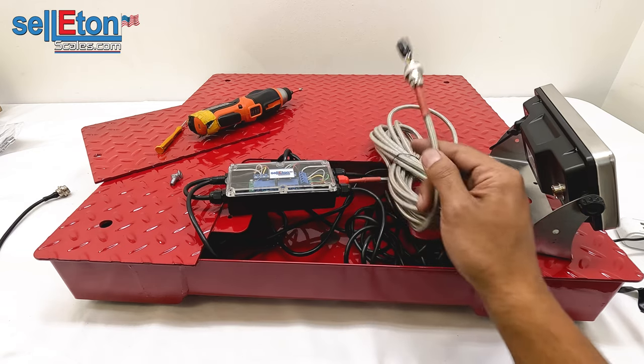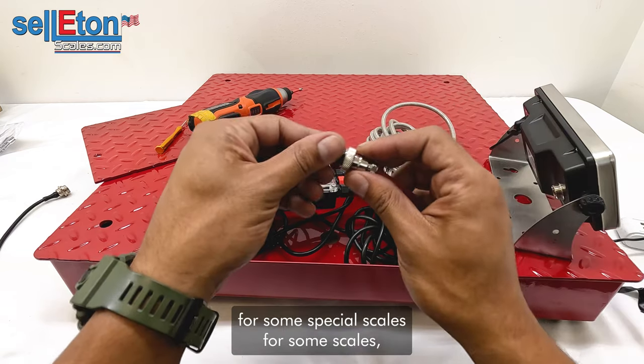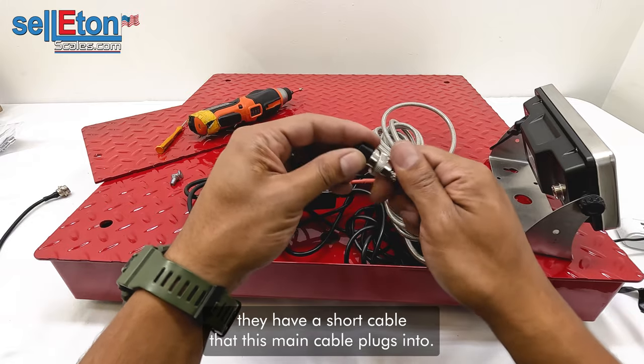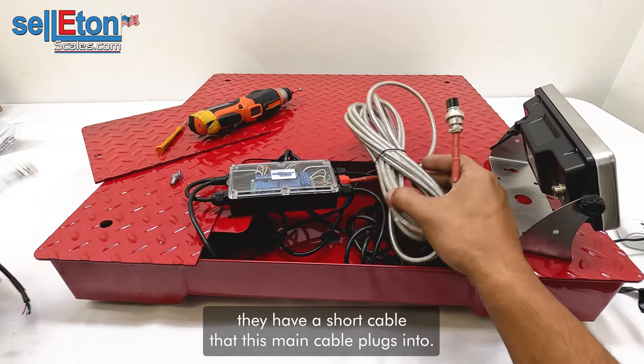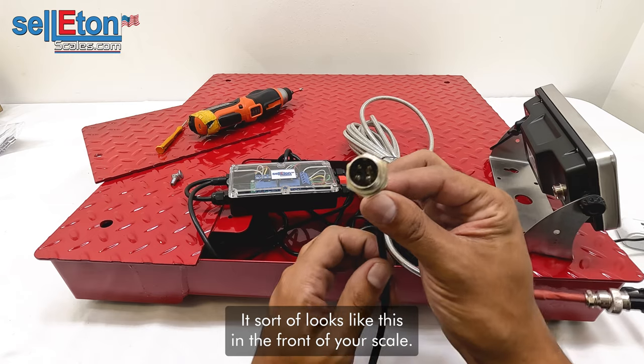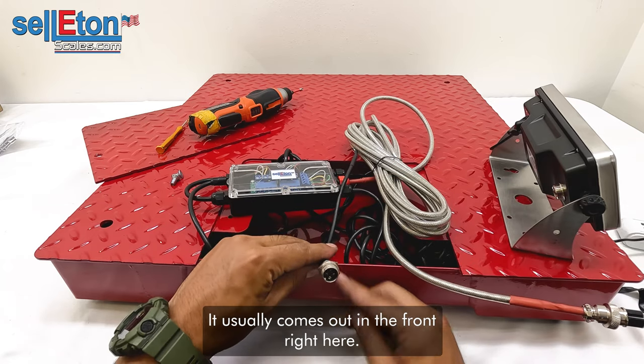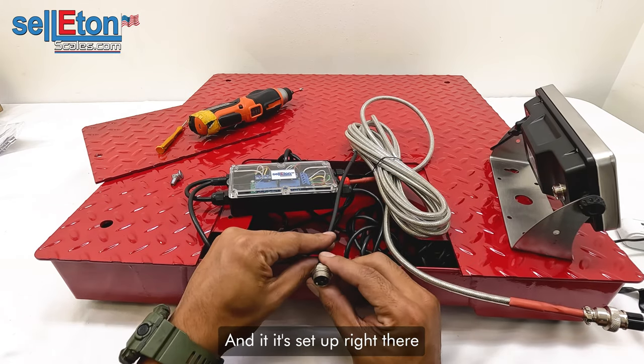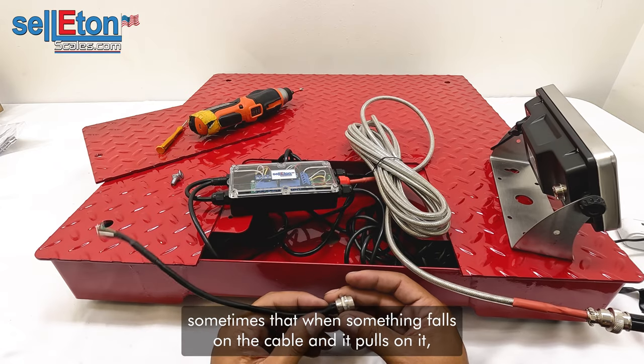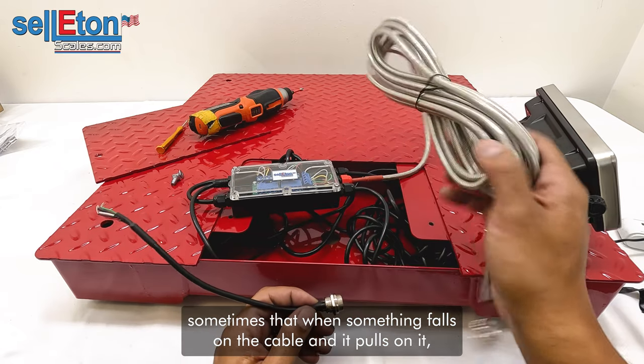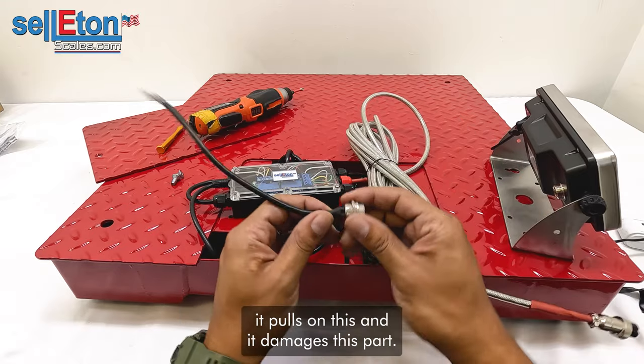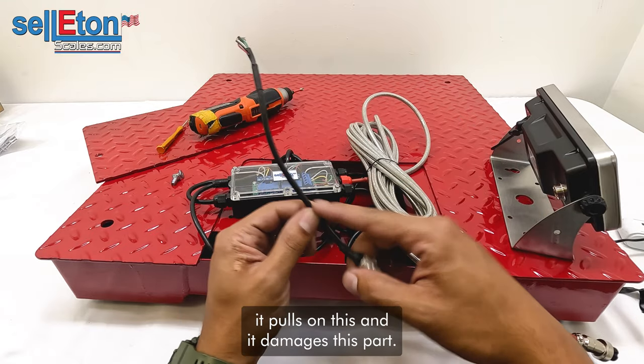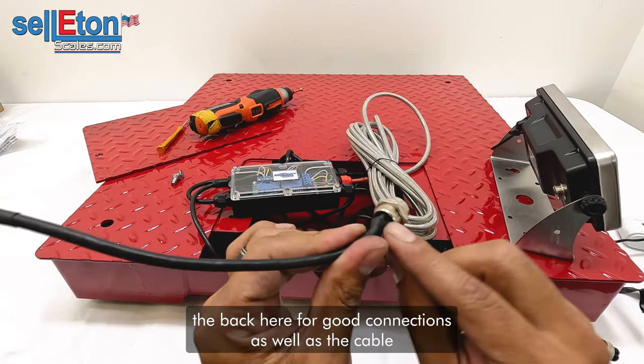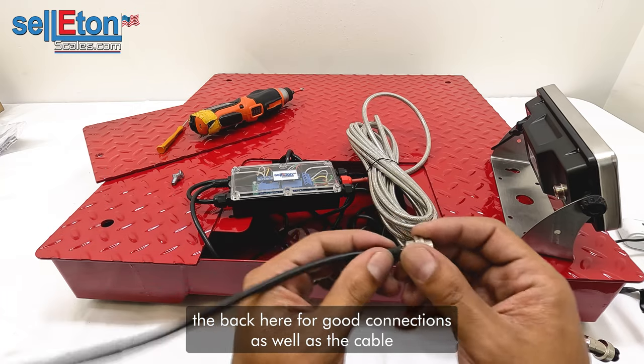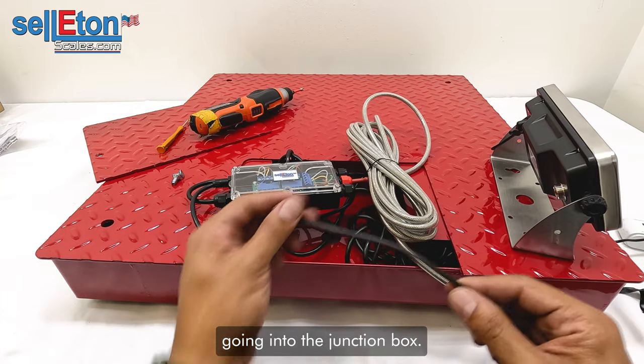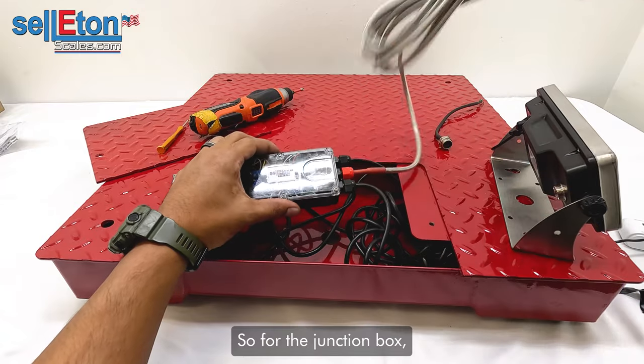Another thing: for some scales, they have a short cable that this main cable plugs into. It sort of looks like this in the front of your scale. It usually comes out in the front right here, and it's set up right there. Sometimes something falls on the cable and it pulls on this and damages this part. So you always want to check the back here for good connections, as well as the cable going into the junction box.